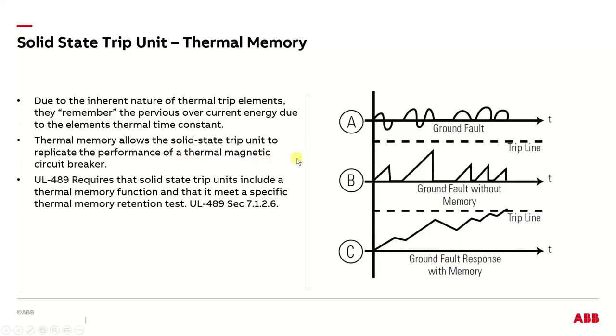The earlier solid-state trip units didn't really remember, they didn't have a thermal memory. So when you got to an overload current that started to pick up, if that overload current suddenly went away, you can look at this picture here, A is your current, and this is the ground fault current, and you can see it goes up and down, up and down, and here's what the breaker's recording. So it sees, okay, I got a spike, and I pick up, oh, spike went away, another one. So it's got all these events going on, which is thermally adding up as damage to the equipment, but the breaker doesn't see it. The breaker's blind. It thinks these are basically five discrete events. When you add memory onto the breaker, it integrates all those together.